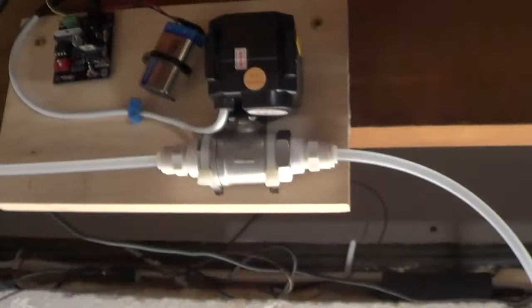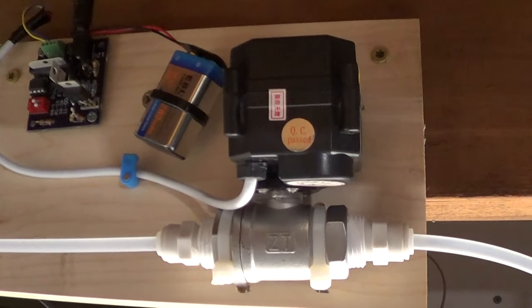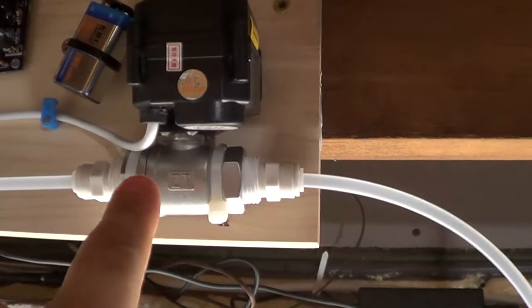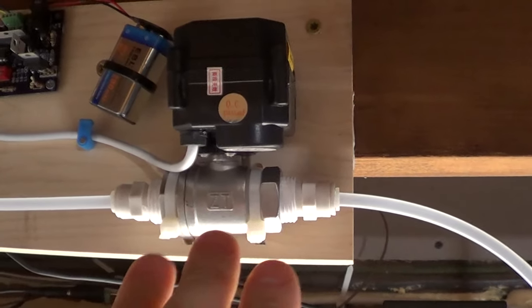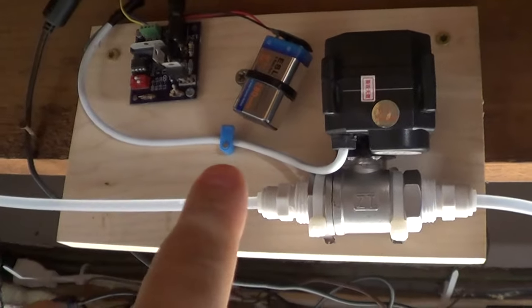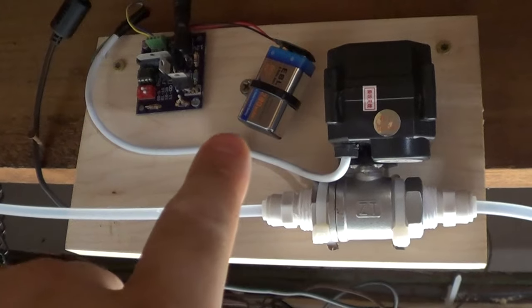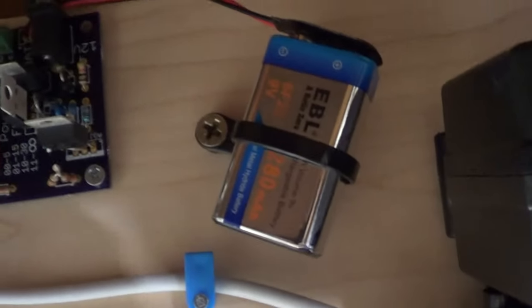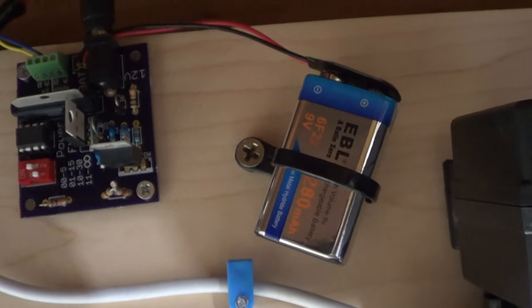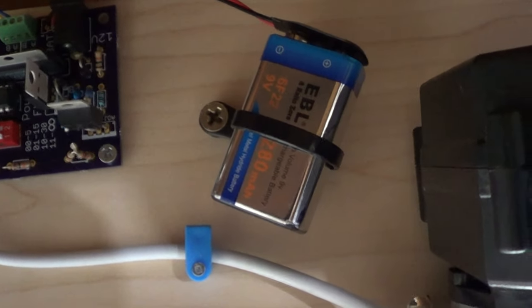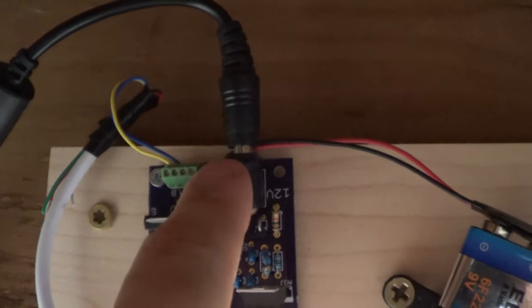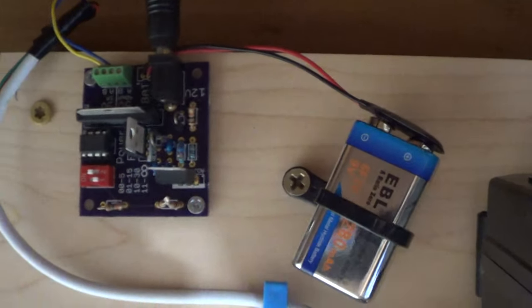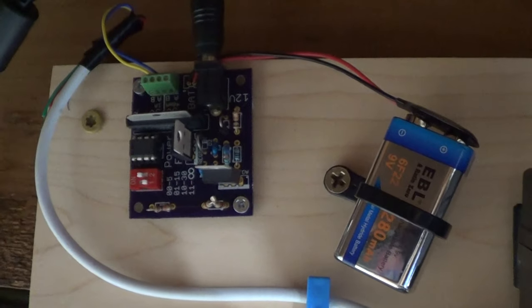And the reason I like this is because it's not putting any stress on the hardware itself here, and this valve won't need to open or close very often at all. And essentially, the only thing we have to be careful of is that this battery doesn't die. Now this battery should last quite a long time. It's a rechargeable battery. It's getting a very small trickle charge while we have our 12 volts of power in, and so that should last for many, many months without any issue.